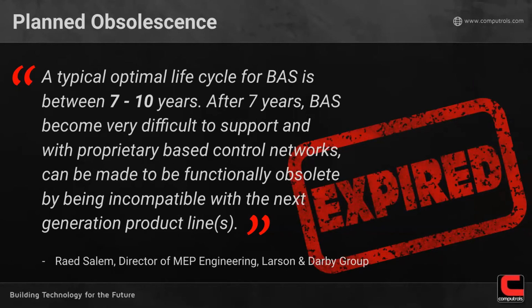Something we look at a lot at Computrols is the life cycle cost of building automation systems. We want to know where that product is in the life cycle, because one of the biggest problems in the building automation industry for the last 30, 40 years has been planned obsolescence, where a manufacturer decides to obsolete a product, a piece of hardware or software, and says we cannot support this product anymore. You'll find there's not really backward and forward compatibility built into a lot of these products. A manufacturer may tell their customer, look, this controller's been out there for 20 years, we have newer technology replacing it, you need to upgrade or we can't support your system.